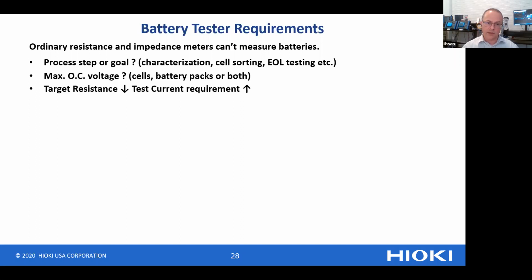And also, what's our target resistance? As our target resistance decreases, our test current requirement increases. This is because of a basic signal to noise ratio issue. We want to have a good signal to noise ratio, so we require a larger test current.